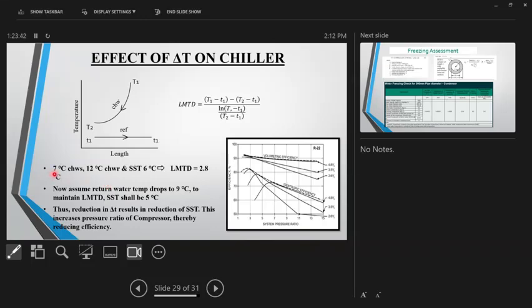Now, imagine a chiller in a commercial building application, with a regular 7 degree supply and 12 degrees centigrade return. If you want this, the manufacturer probably needs to boil the refrigerant at 6 degrees centigrade. SST is saturated suction temperature. So to give you 7 degrees chilled water temperature, the manufacturer will boil the refrigerant, maybe R134a or whatever, at 6 degrees centigrade. So there is an approach of 1 degree centigrade, correct? Nowadays, there are obviously evaporators available with a much lower approach than this. But for this example, assume that the refrigerant is boiling at 6 degrees centigrade.